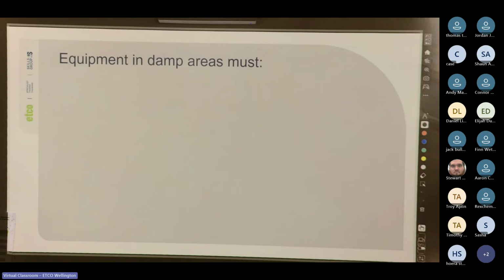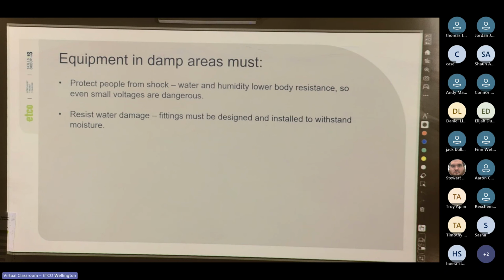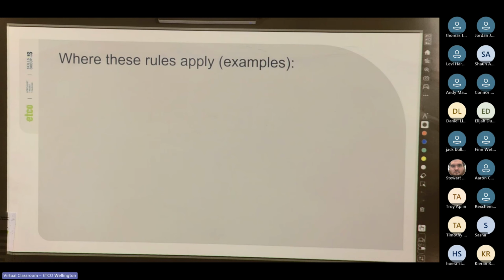Cool. So, equipment in damp areas. There are certain things that the equipment in these damp areas must do. They must protect people from shock. Water and humidity lower body resistance, so our own, and the resistance of any material. So even small voltages can be dangerous. They must resist water damage, so they must be designed and installed to withstand moisture. If it's designed for exterior, it will say it's designed for exterior. The general wiring rules still apply. The requirements for damp situations are extra for damp areas.